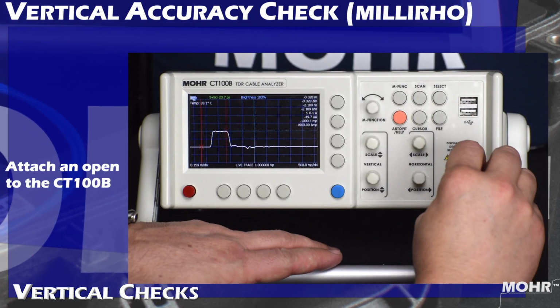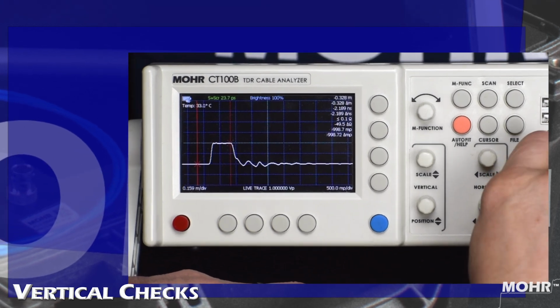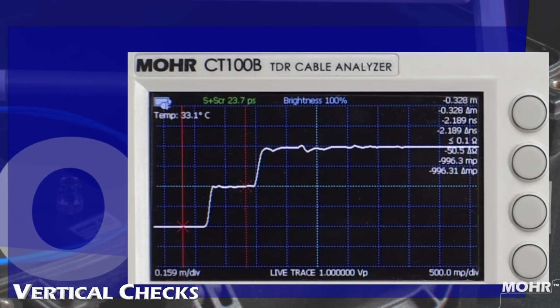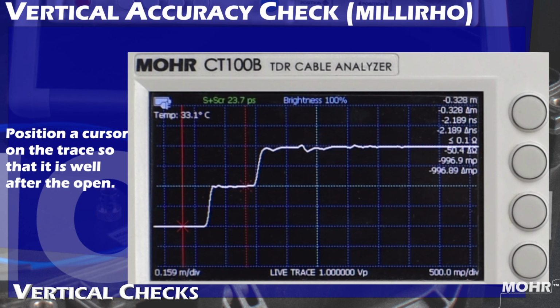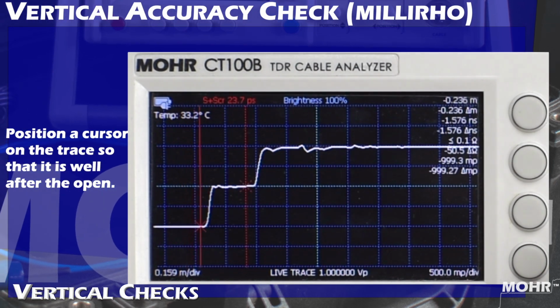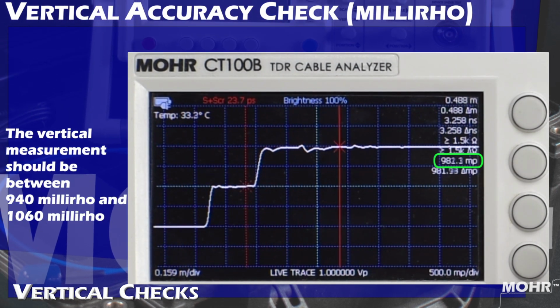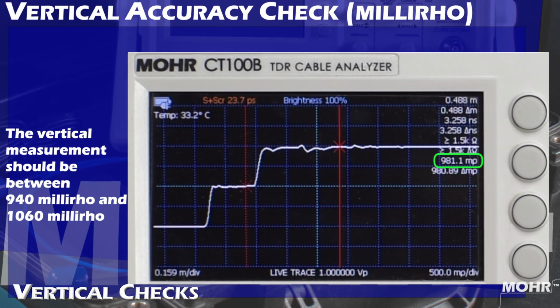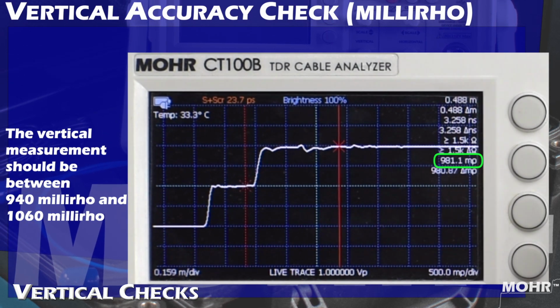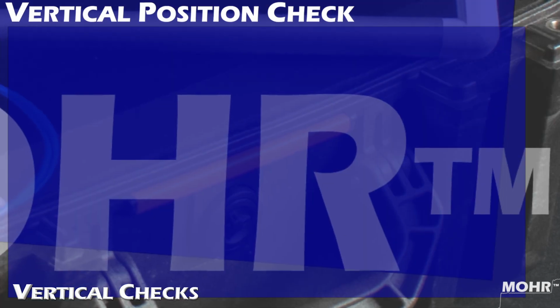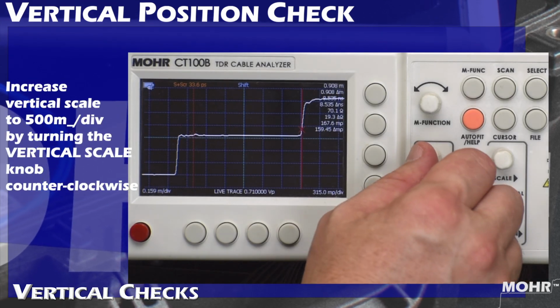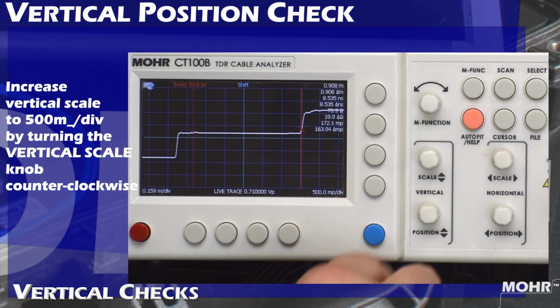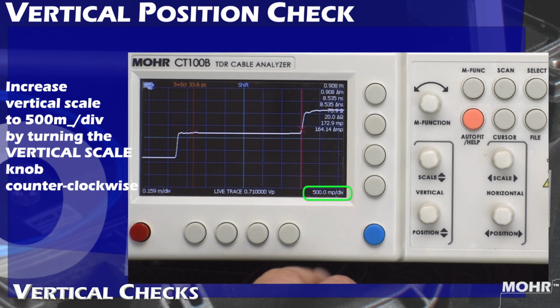The vertical accuracy check. Attach an open to the CT100B, and position a cursor on the trace so that it's well after the open. The vertical measurement should be between 940 millirho and 1060 millirho. For vertical position check, increase the vertical scale to 500 per division by turning the vertical scale knob counterclockwise.